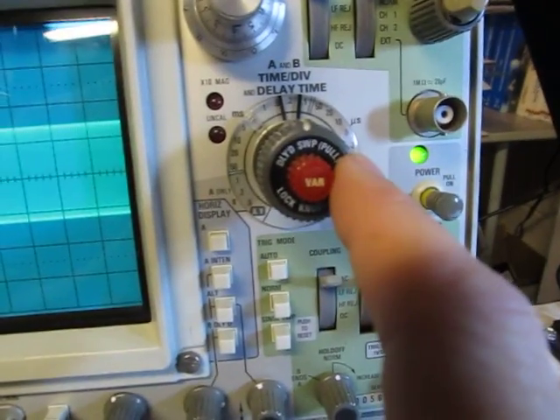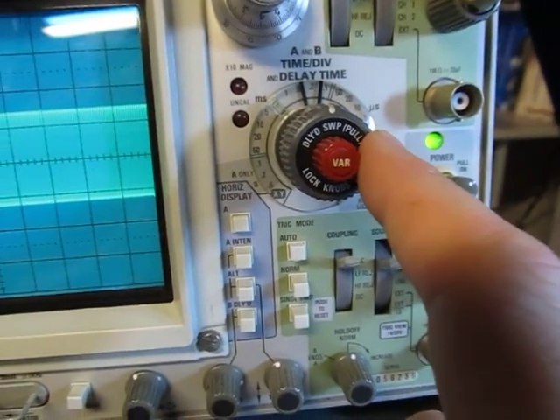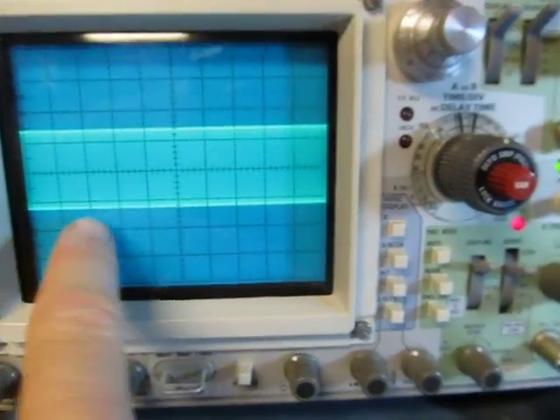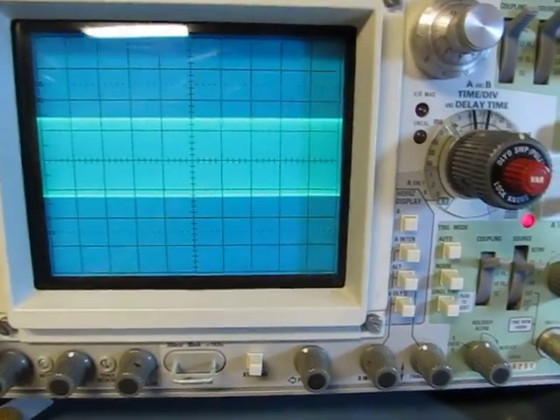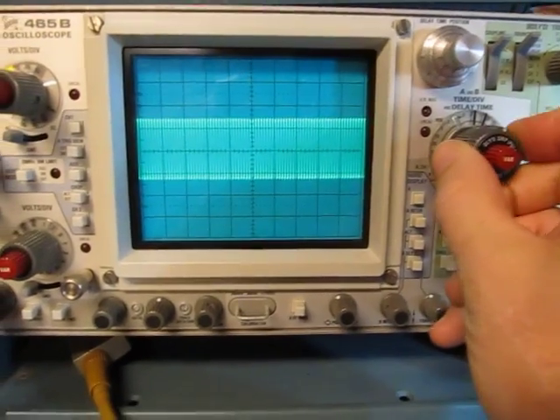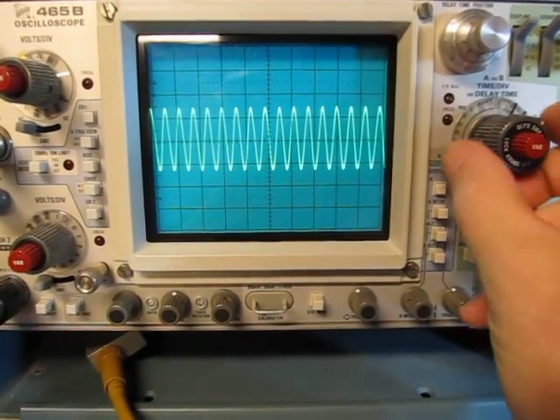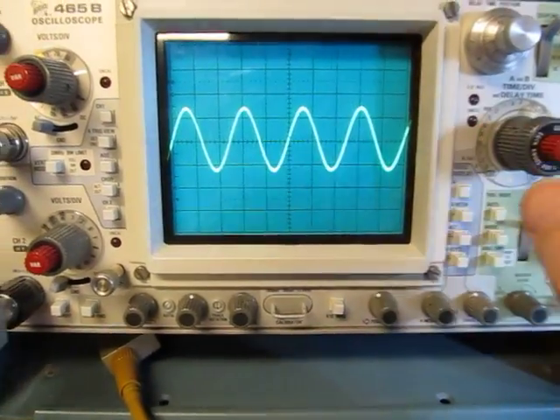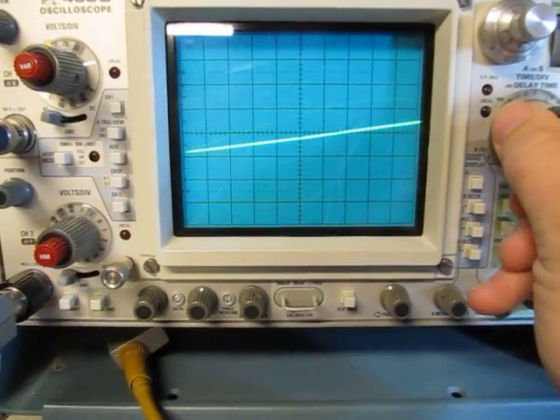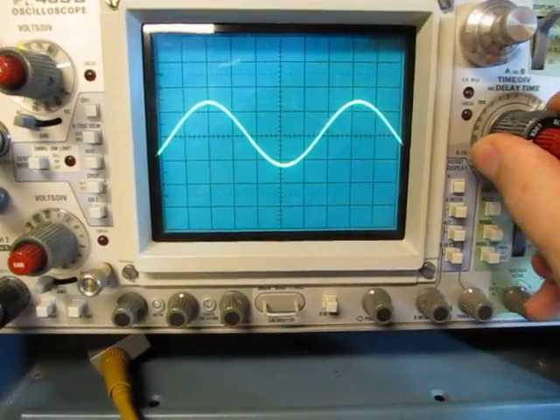Now we need to adjust our horizontal time base. The horizontal time base on the scope basically controls how quickly we're moving the beam across the screen. And the faster we move it, the more we'll stretch out the waveform. So you'll notice I'm turning this up faster and faster. I'm stretching that waveform out further, further, further. So how fast do we want to go?